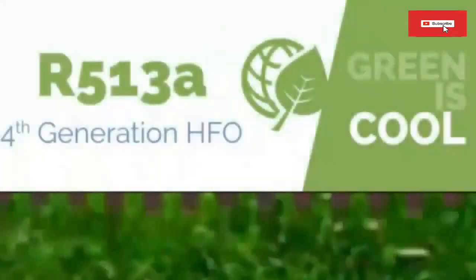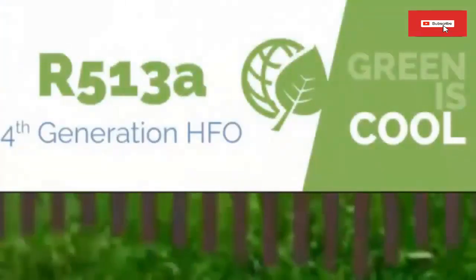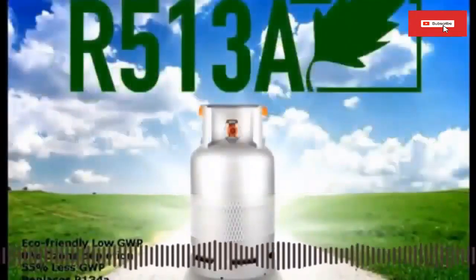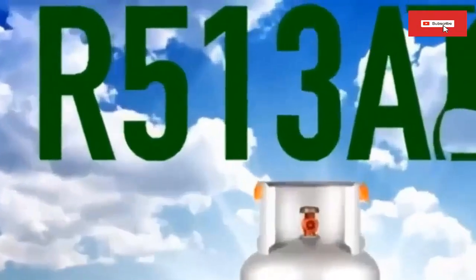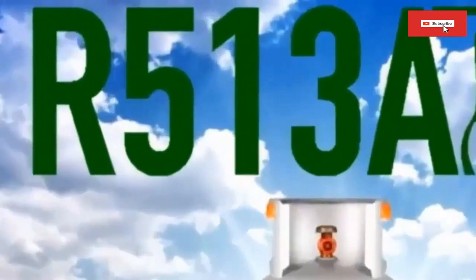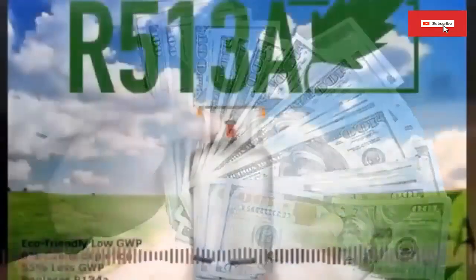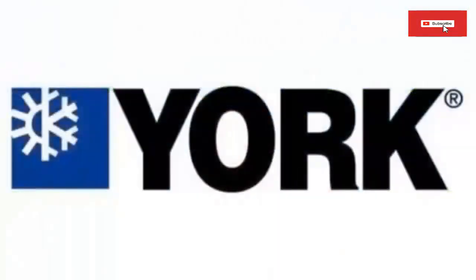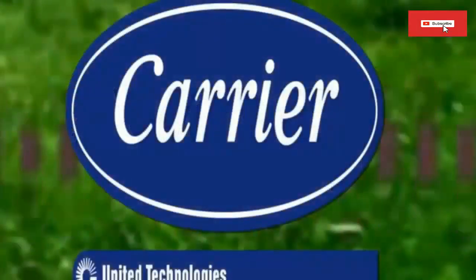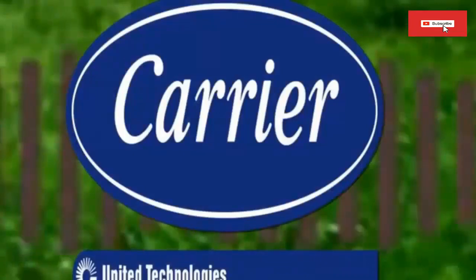7. R-513a refrigerant is an azeotropic, non-glide blend. 8. By providing efficient R-134a equipment that is future compatible with R-513a, the long-term investment customers make in their equipment is protected. 9. York Company's chiller offering of R-134a products that can be used with R-513a provides peace of mind with the initial investment. 10. Carrier has announced that its AquaEdge 19XR and 23XR, and AquaForce 30XV and XA chillers are compatible with R-513a refrigerant.